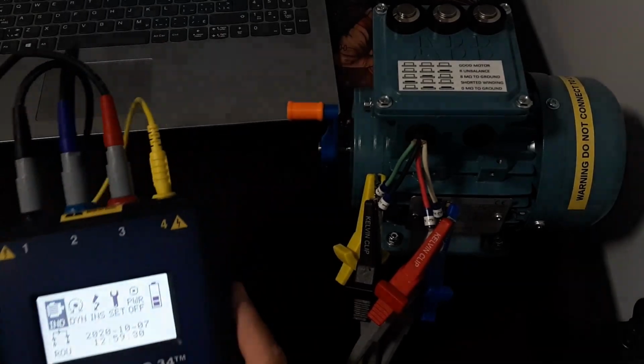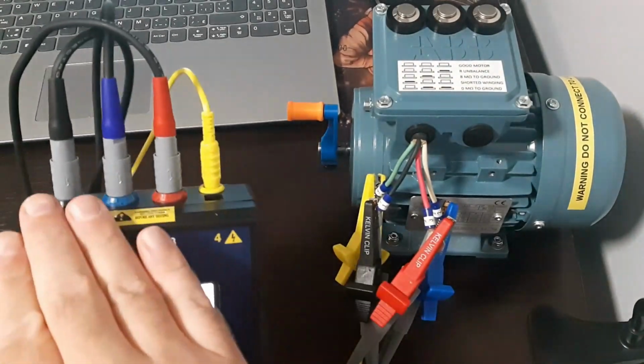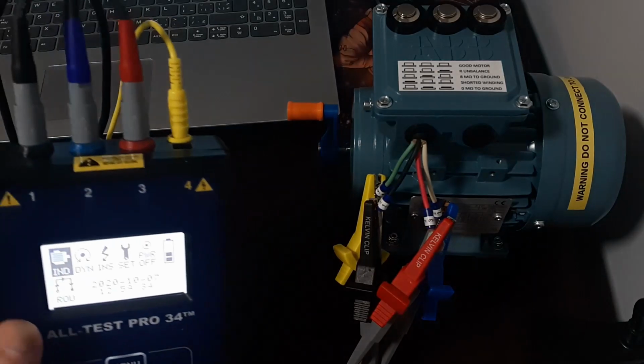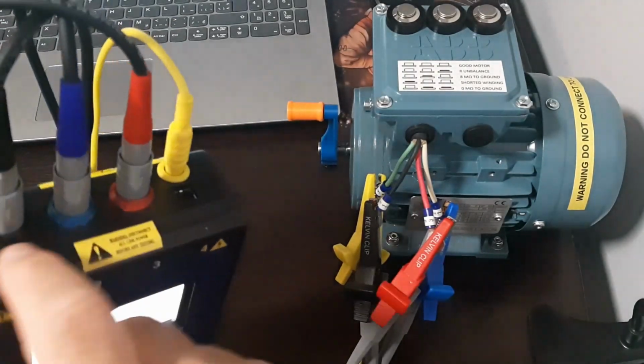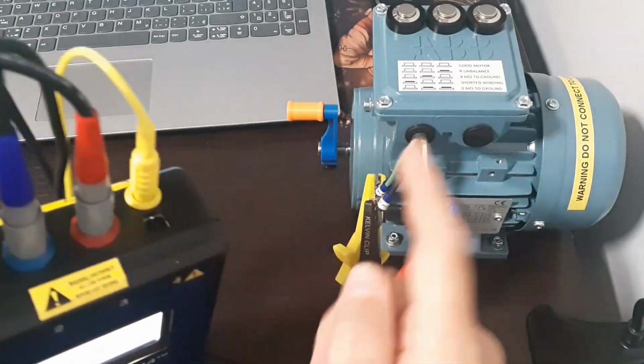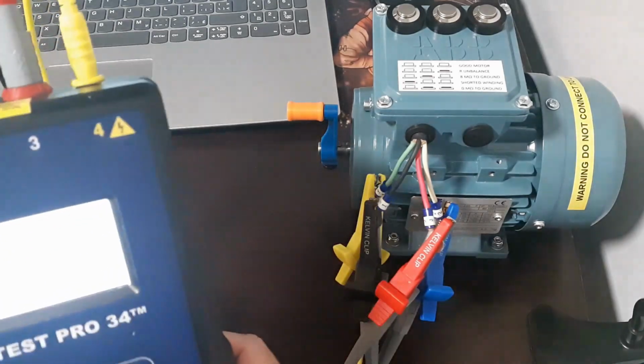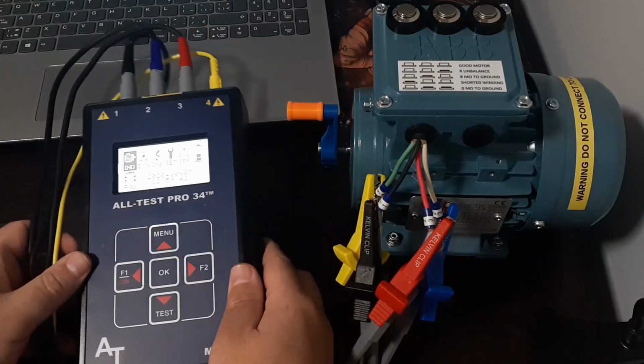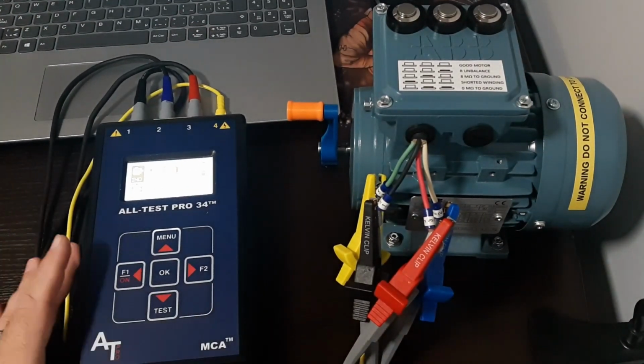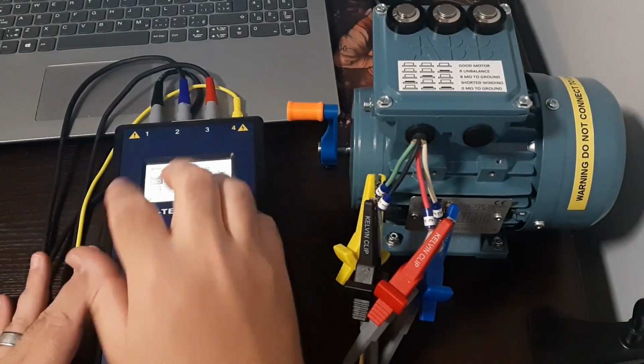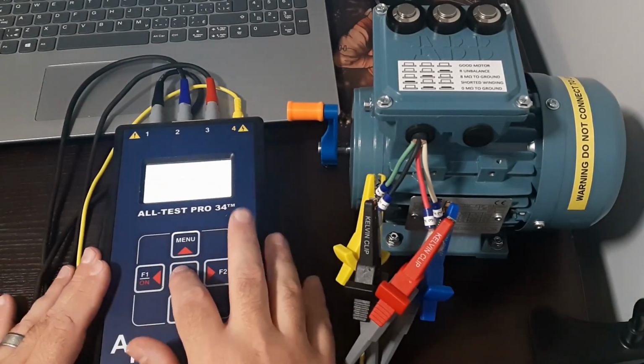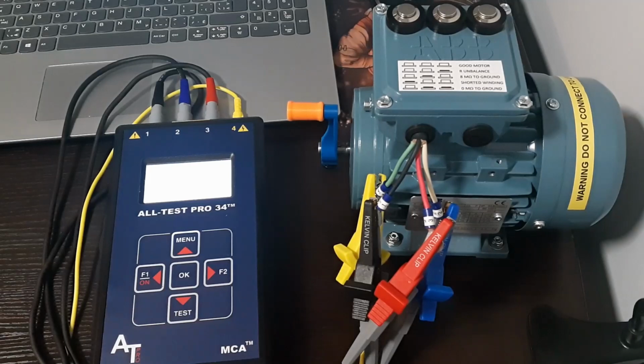Okay, so we're ready to test this motor. Now, as you can see, I've connected in the leads here. We've got black, blue, red. They're labeled right on here, the yellow, the ground lead. It's all labeled, nice and simple, so you can do that. And I've got these clipped in here. So we're going to go on the induction test here, and it'll actually ask us whether we want to do all the other tests here.